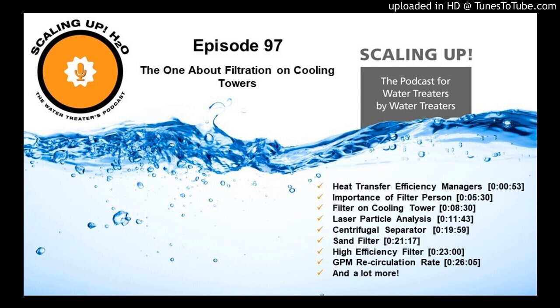Okay, the basic concept with cooling towers, as we all know, is that they pass water across large volumes of air, and it allows the water to evaporate and cool the water from 95 degrees to 85 degrees or so. So we have to put a lot of air through water. Most often, contamination in cooling water systems comes from the particles that are washed out of the air. So any cooling tower is continually washing dirt out of the air. How bad that deposition can be depends on what environment you're in, and it also depends on a lot of things like the cycles of concentration that you maintain. But generally, a cooling tower needs to have a filter to pull out the particulate in there.